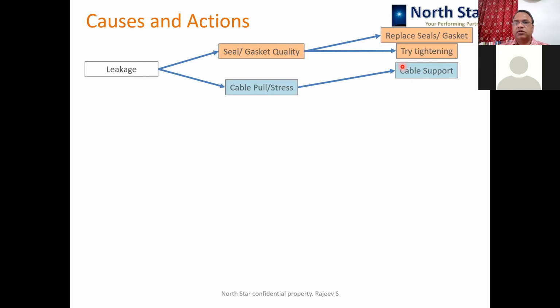There are also epoxy compounds available, which are put on the gaskets as a coating, and you can plug the leaks with them. But again, after maybe 2 or 3 years, the leak will start coming from there. Then cable supports are to be carefully maintained, or their tension properly adjusted, so that they are not pulling the bushings down or up, which may make the bushing fail.